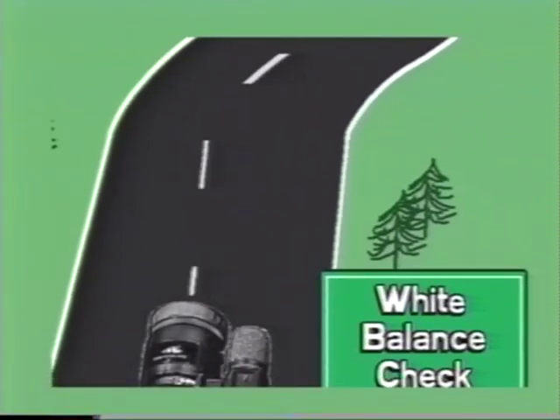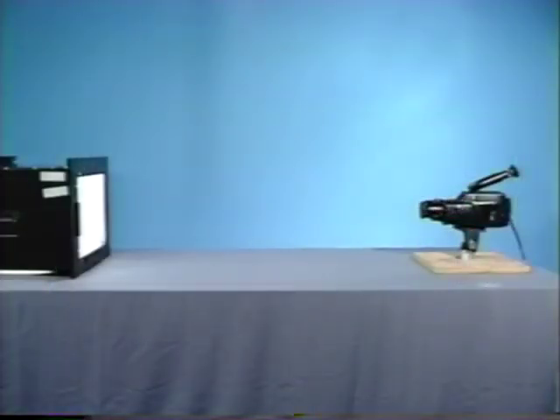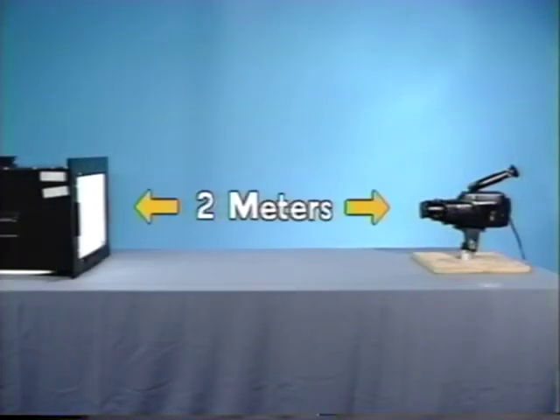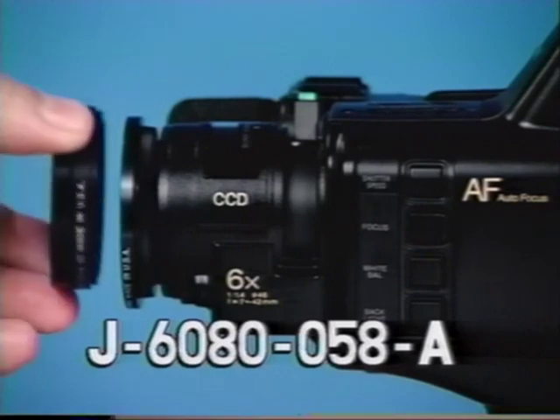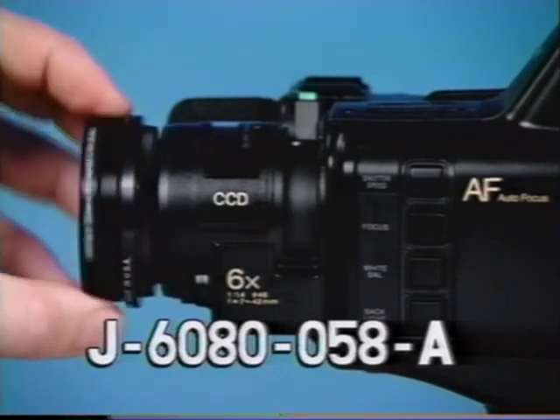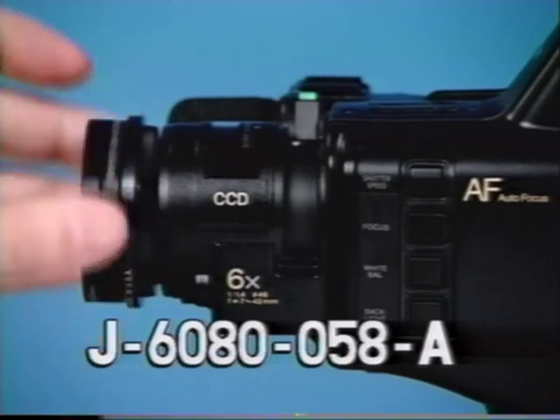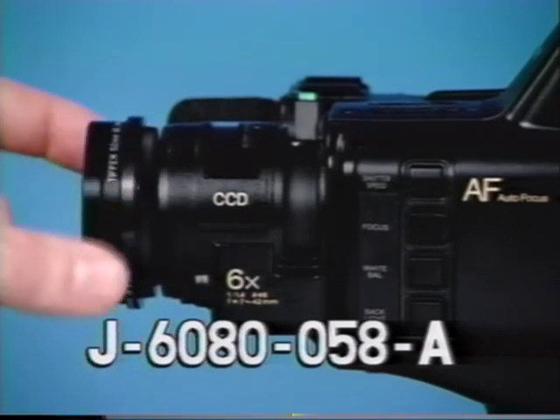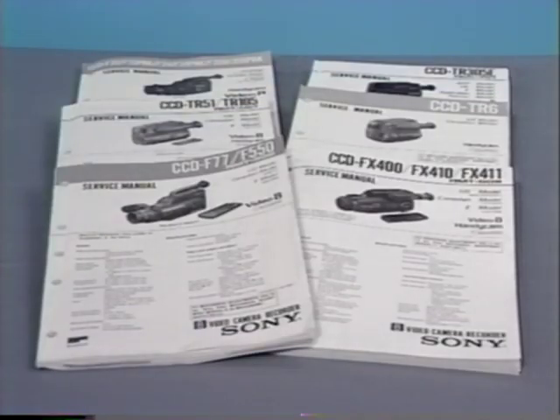After determining that all focus modes are functioning, next check the calibration of the camera's auto and preset white balance adjustments. Position the lens focal mark approximately 2 meters from a light box with an all-white pattern. Install a Sony C14 color conversion filter combination or 80A and 82 filters in front of the lens to simulate outdoor light.